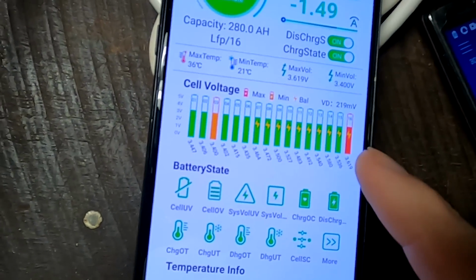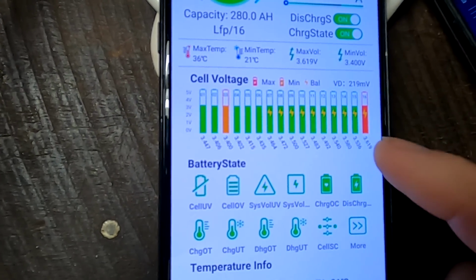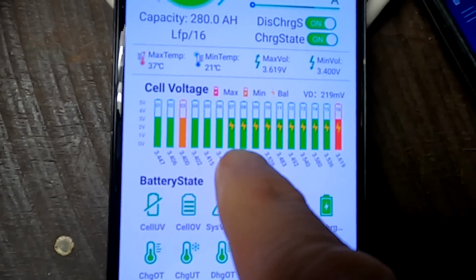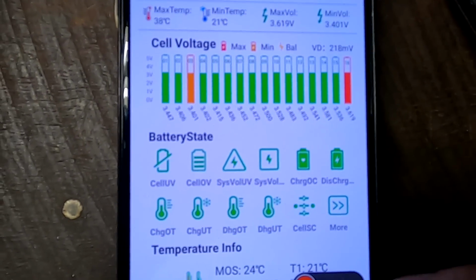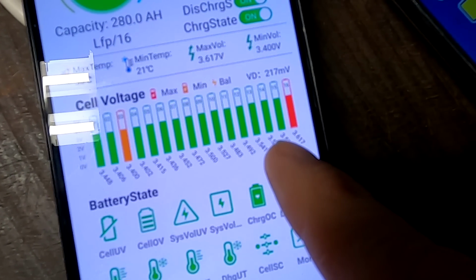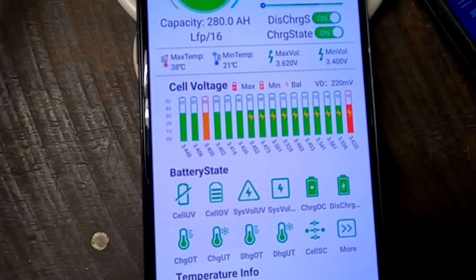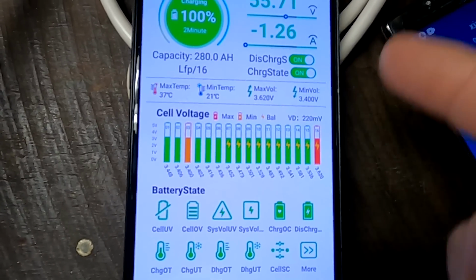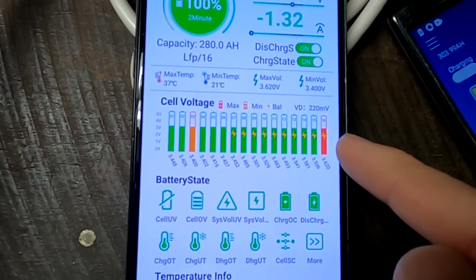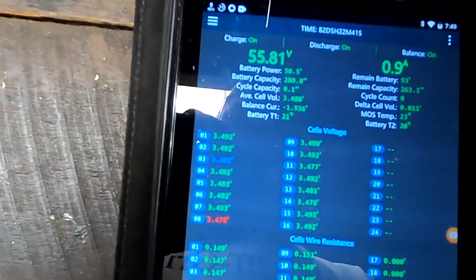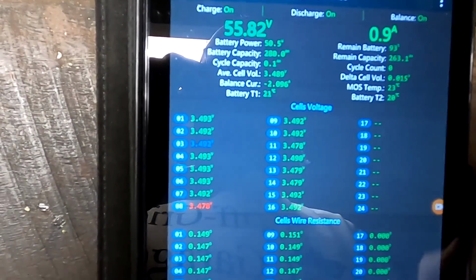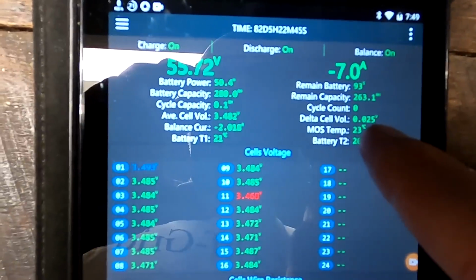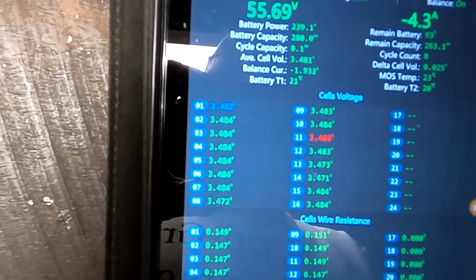And we've got a similar situation in the Heltec BMS on the bottom shelf. You can see all these battery cells get balanced now, and cell number 16 is also high here with 3.62 volts. Sometimes the BMS turns off the whole battery bank because this cell is over 3.65. And only the JK BMS has only 15 millivolt deviation. It is balancing right now.